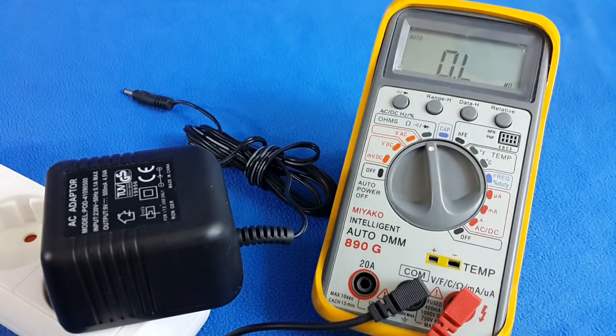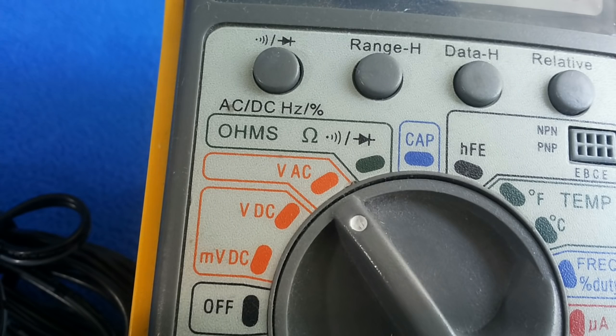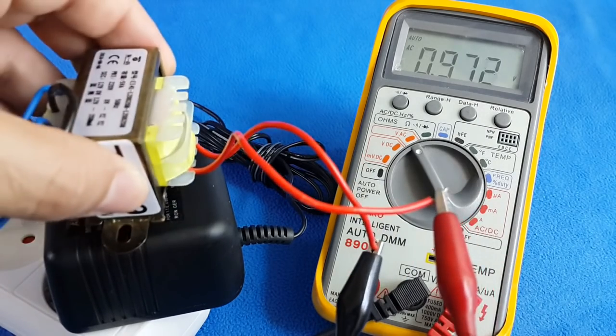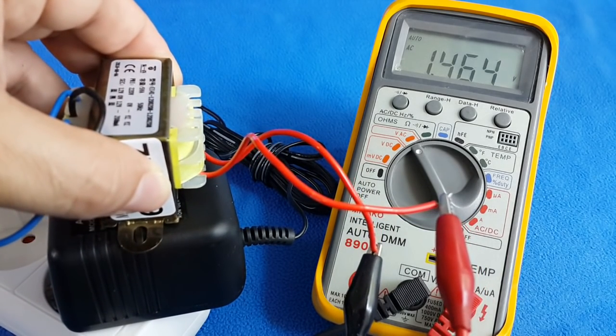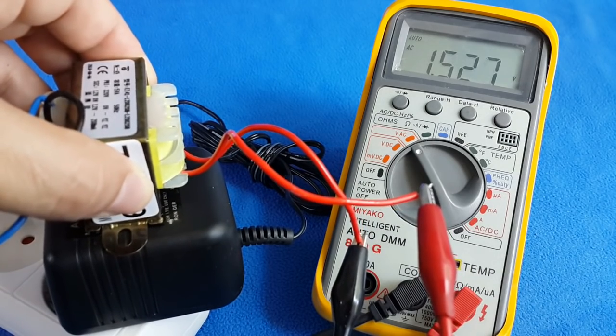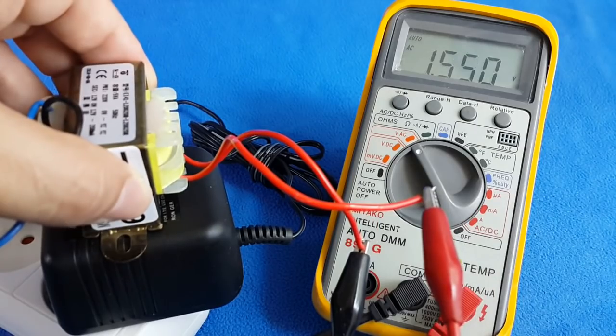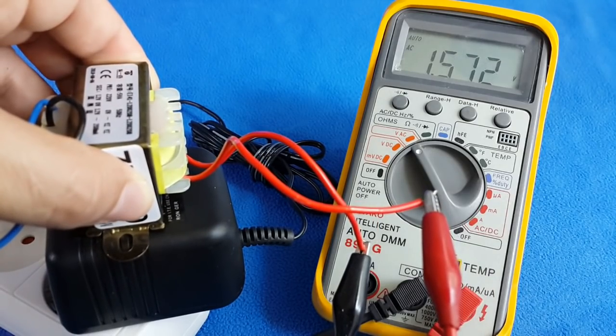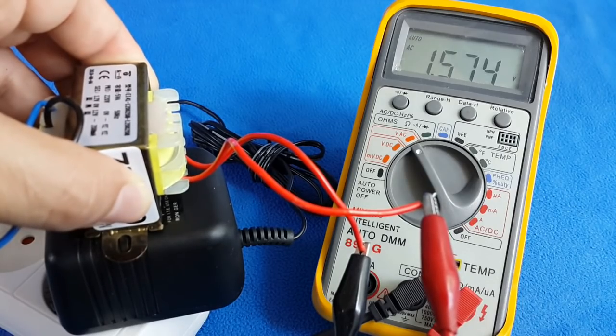Using other transformer, I can make an induction to my transformer under test and find out if it is working fine or if there is a short circuit on it. What I have to do is just get close and go away, and I will see a change in the output voltage. Let's start with the primary because it will generate more voltage. The digital multimeter must go to AC. The output voltage will increase as I get closer to the other transformer.